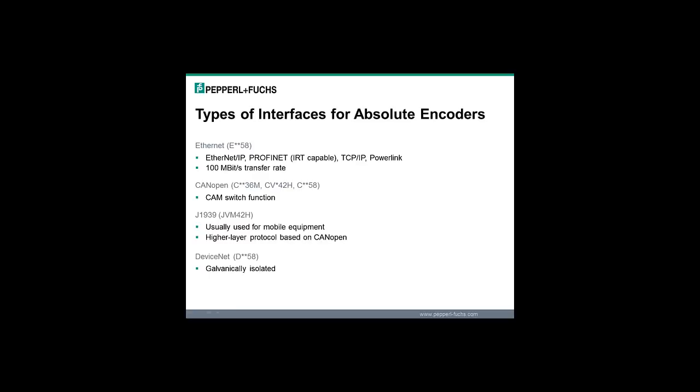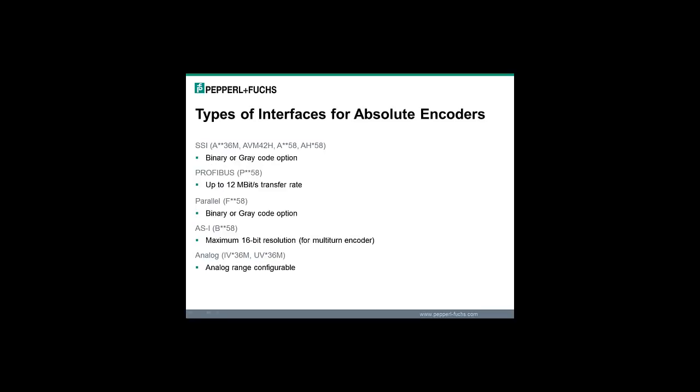When selecting an absolute encoder, the protocol or output also needs to be selected. The series nomenclature first letter indicates the protocol of the absolute encoder. E is for Ethernet, C is for CANopen, J is for J1939, D is for DeviceNet. A is for SSI, P is for PROFIBUS, F is for Parallel, B is for AS Interface, I is for Current Analog, and U is for Voltage Analog Output.